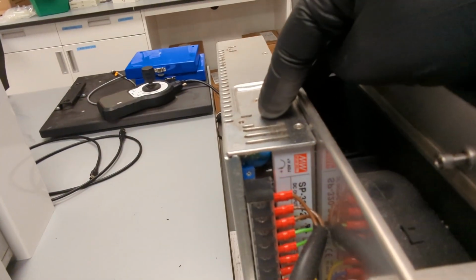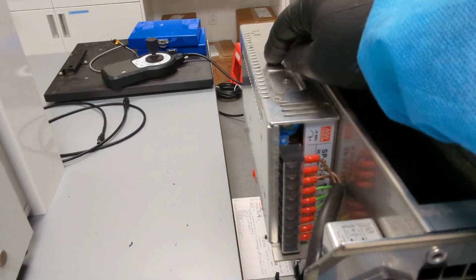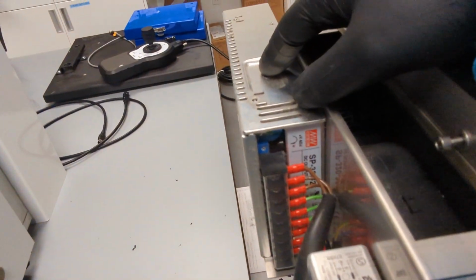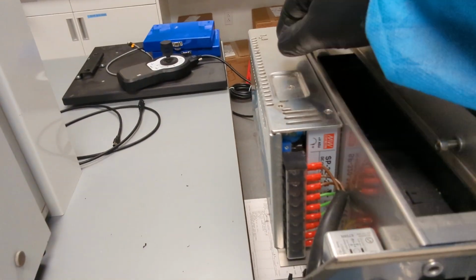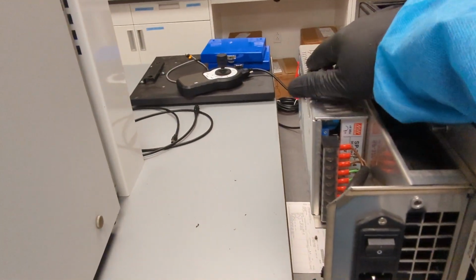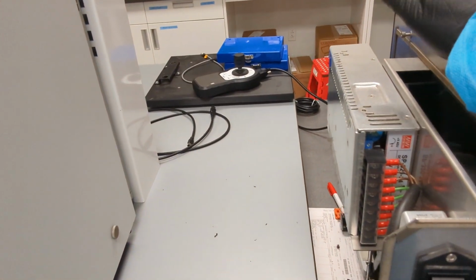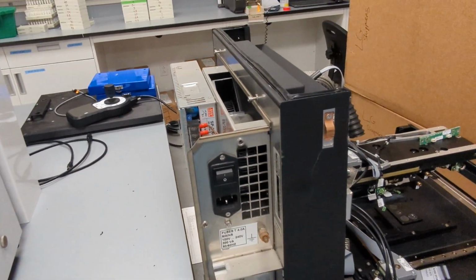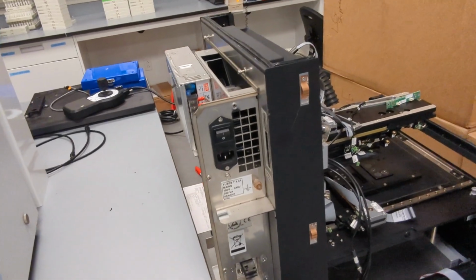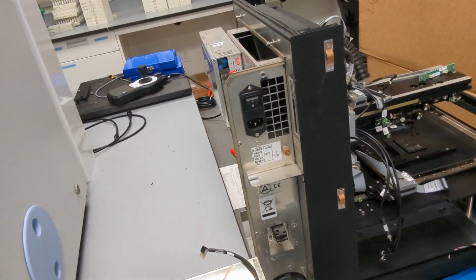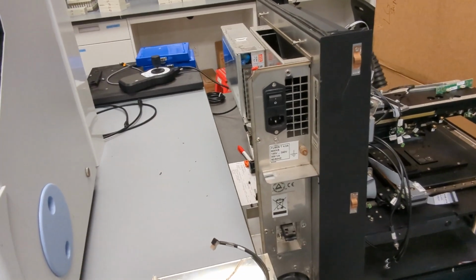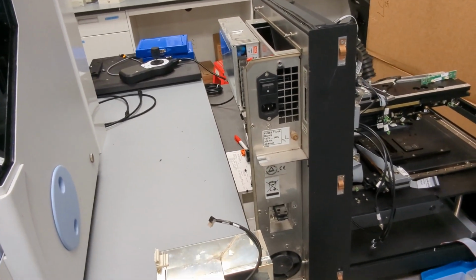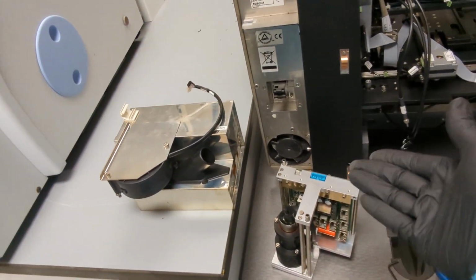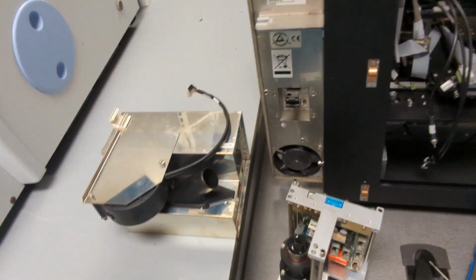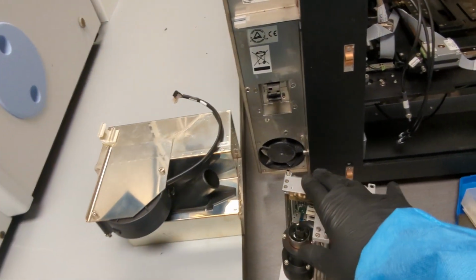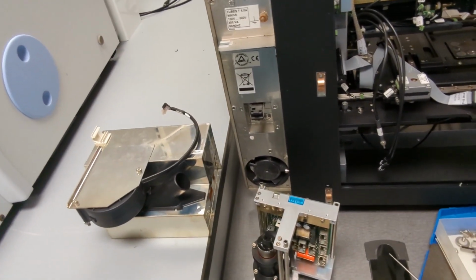power supply here. This is just a Meanwell supply, probably non-proprietary. I'm trying to read the label here. It looks like it's a 24-volt supply providing up to 13 amps. So pretty beefy supply, but that's going to be providing all of the DC voltage to this instrument. And then, as I was saying, for those high voltage needs, like for the flash lamp and the PMTs, that 24 volts is going to get stepped up, and then further stepped up by the multiplier circuits to at least 1,000 volts for the PMTs, and probably about the same for the xenon flash lamp. Maybe more, but in my experience, they do tend to be anywhere from 300 to 1,000 volts, although this guy does look like a pretty large lamp.